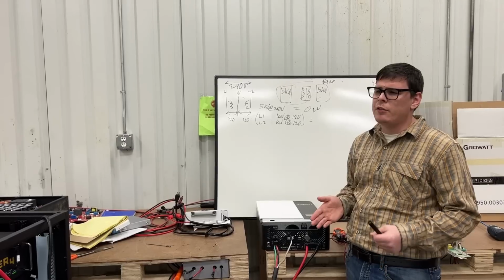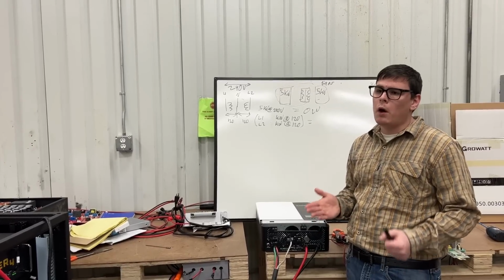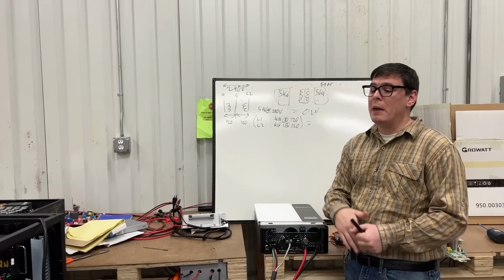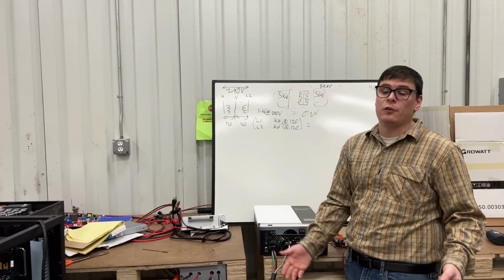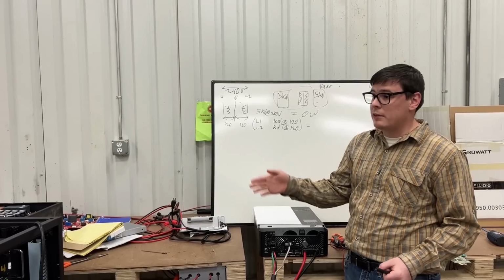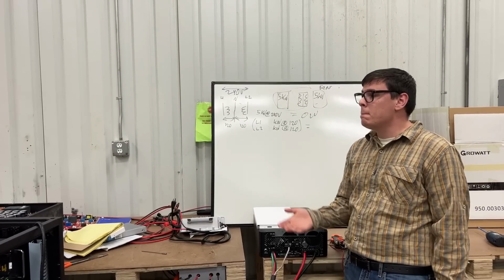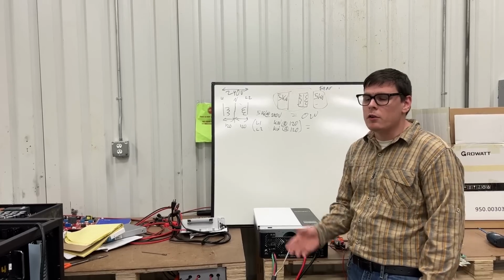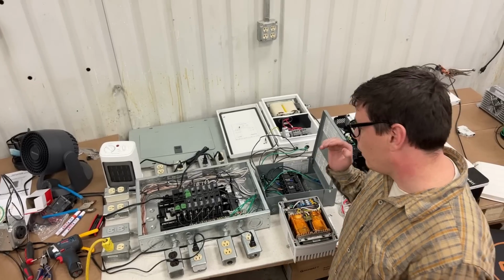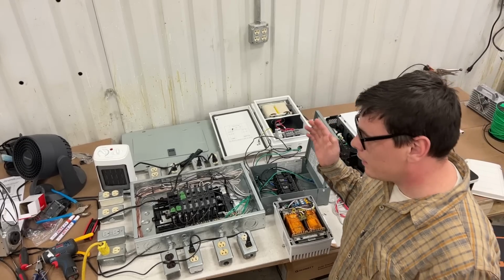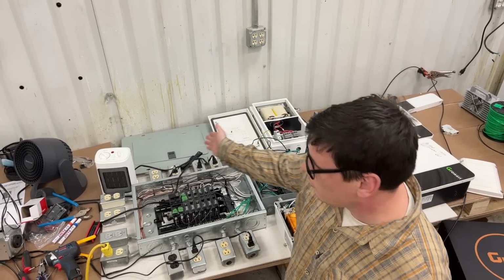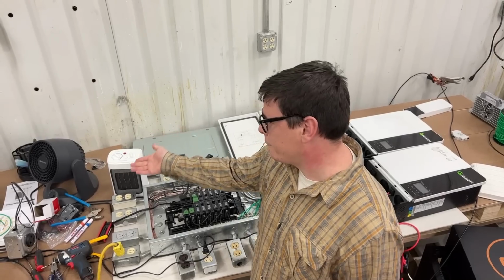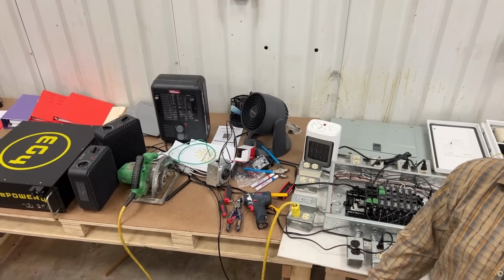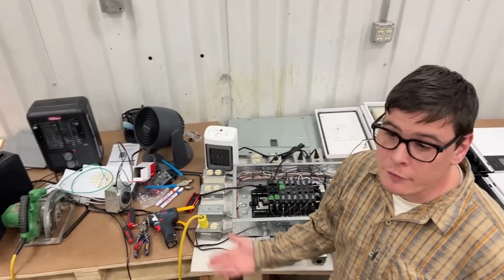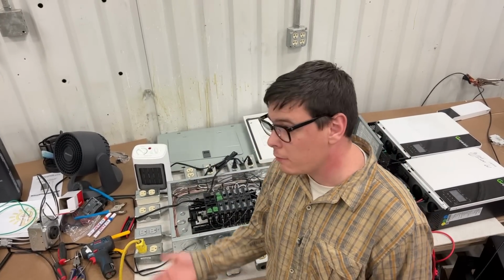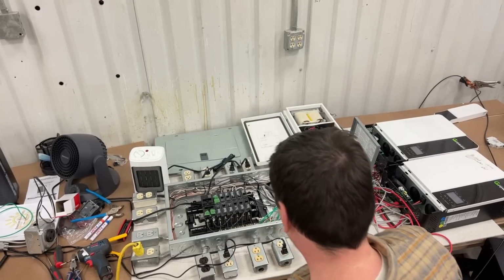But the reality is that if you really want to have double protection, other than making sure you size your transformer right and you balance your loads, if you want to have double protection on top of that, there's a way to do that. And so we're going to show you guys that in just a second. Okay, so I've got a bench here, and from an off-grid perspective, this is a dystopian horror film. I mean, we've got like 5 electric heaters. I mean, I threw mine away 10 years ago.